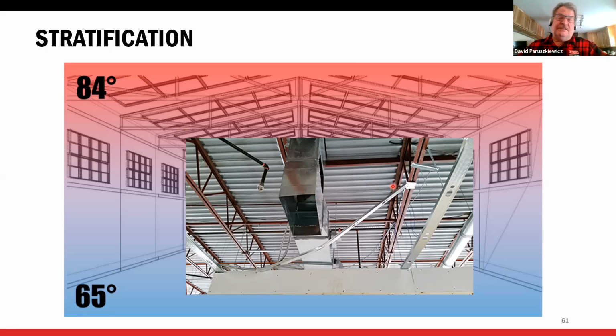Long setbacks, we set it down to 50 degrees at night, 55 degrees at night. You come in this morning, it was 16 degrees last night, right? So that burner comes on and we've got to go from 55 all the way to 75. It's going to run a 20 degree rise. And during all this long run time, the stratification gets really, really big. I start to park all this warm air up here. It's really cold down here for being off all night. So I start to stratify really bad.